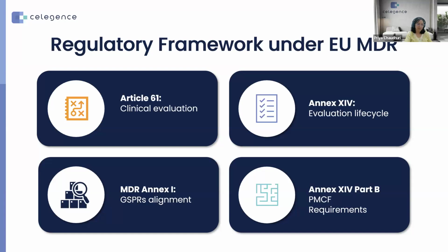It's not just a one-time activity of getting CE marked. It should be throughout the life cycle of the device. So this is especially important for dental implants, where longevity and patient-specific factors can dramatically affect the performance over time. And while we are evaluating the device, every data point that we collect should be fed back into the general safety and performance requirements, otherwise called GSPRs, in Annex 1. These cover everything from biocompatibility, the risk of contamination, any kind of mechanical failure, risks from packaging, and especially the clinical performance.